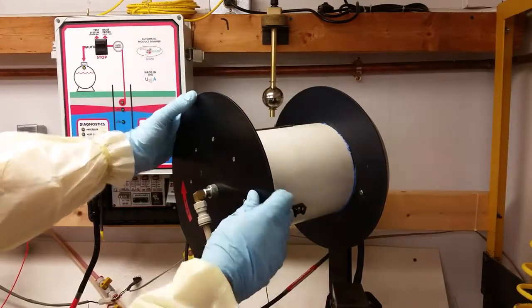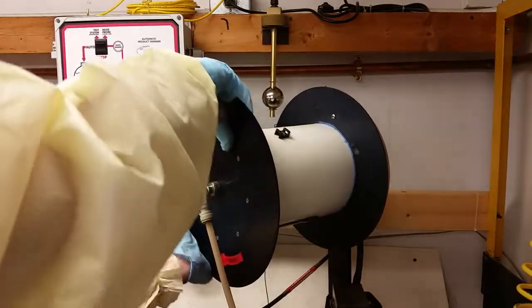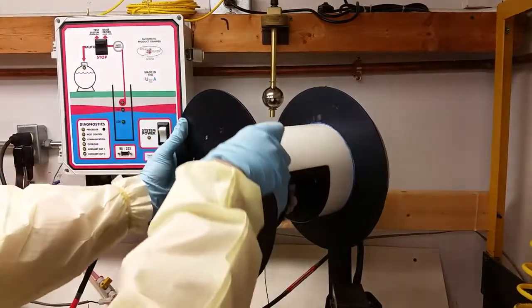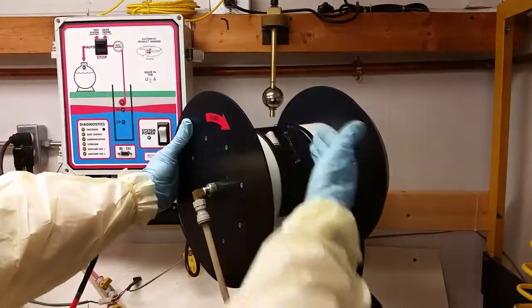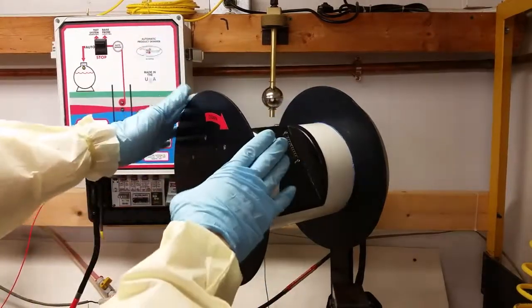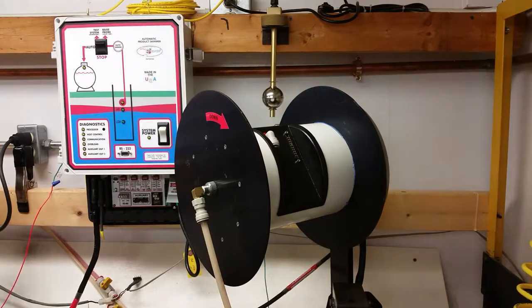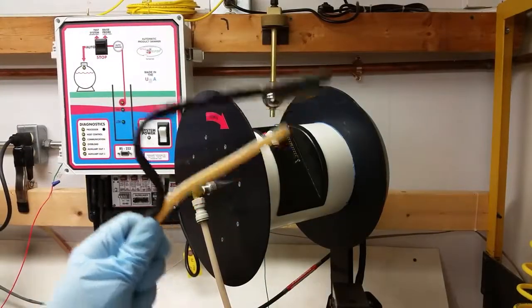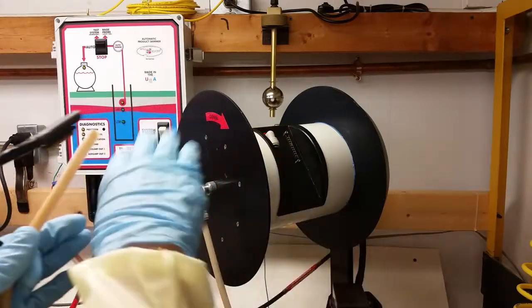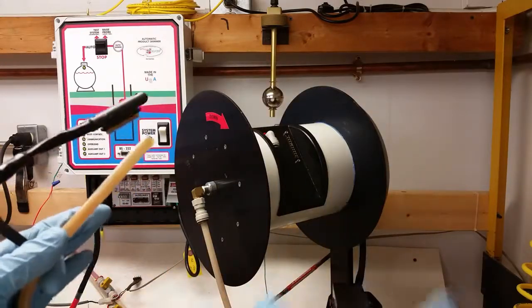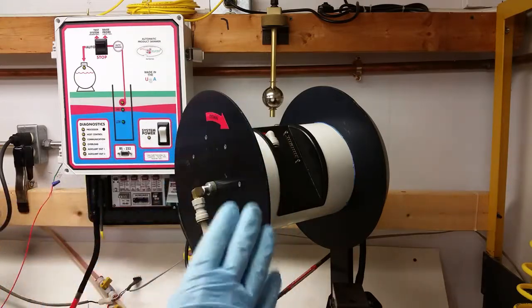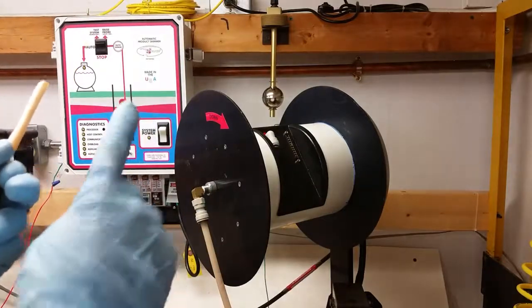So we want to turn this 1/2 to 3/4 of a turn. And doing a little more than that isn't going to hurt anything, especially if it makes it any easier for you to make your connections at your connector pocket here. So that's about 3/4 of a turn. And we are going to reconnect our probe right now. Now, to compensate for that 3/4 of a turn in the upward direction, we need to manually wrap the probe around the auto seeker twice. That way, if it ever does get back down to its fully downward position, the limit switch will engage before the probe starts winding on backwards.